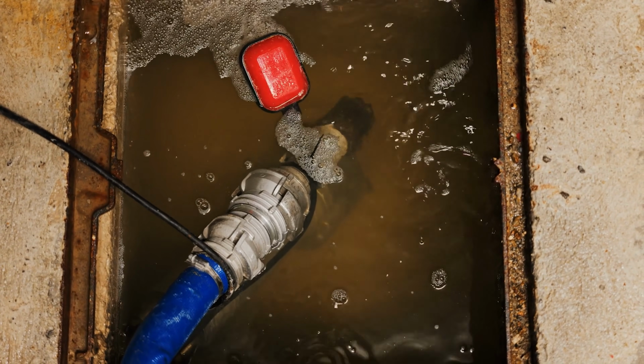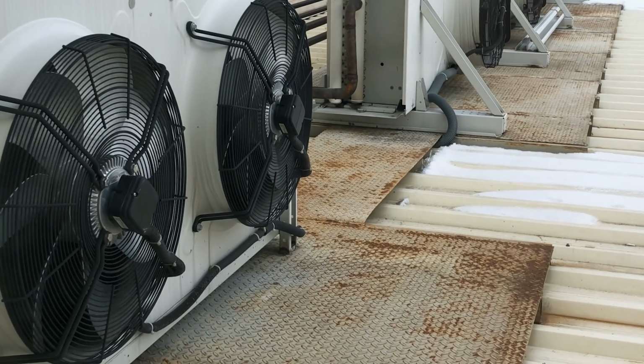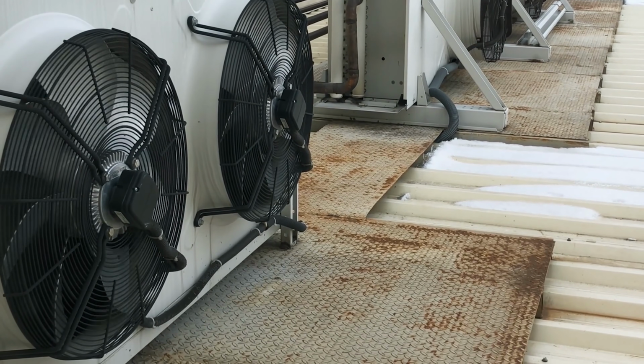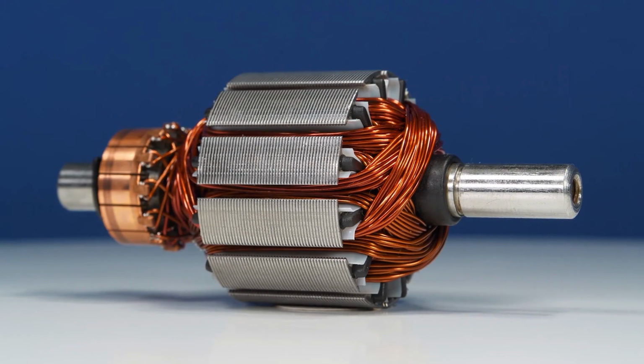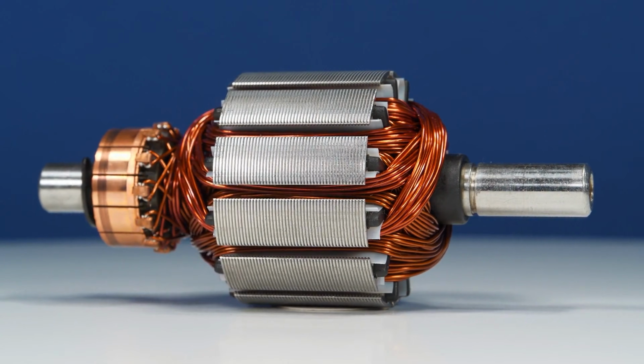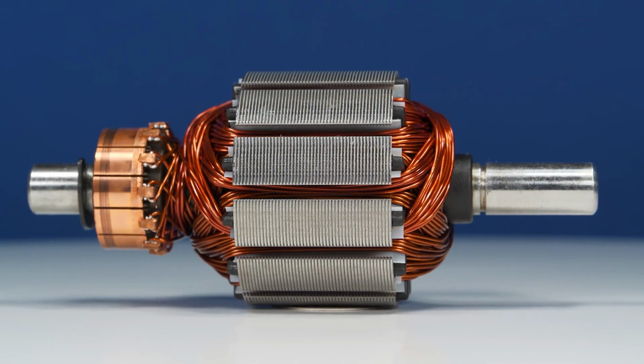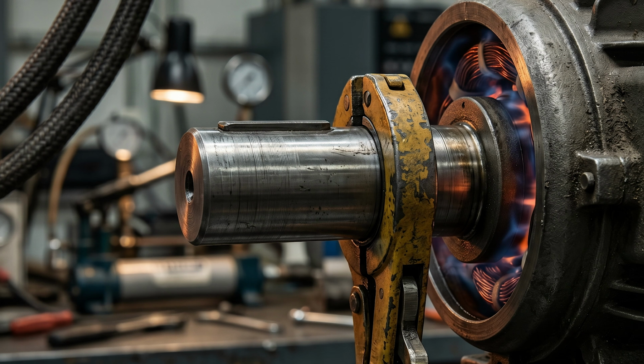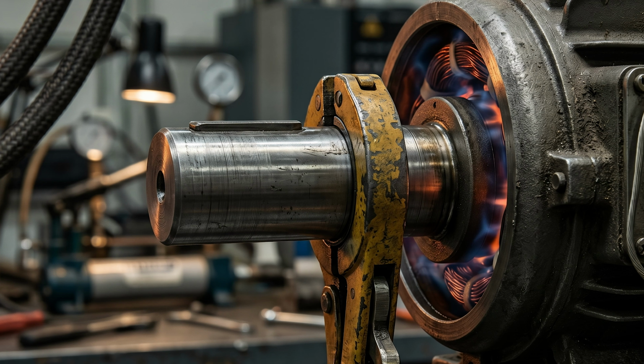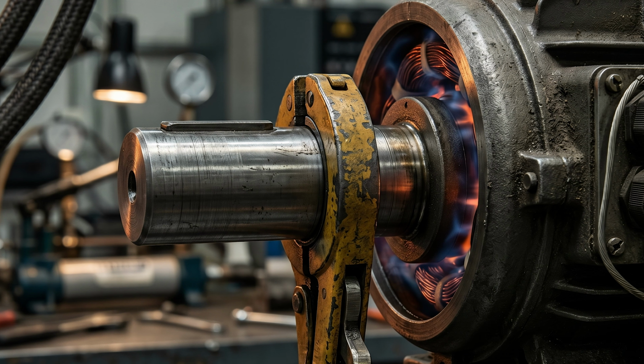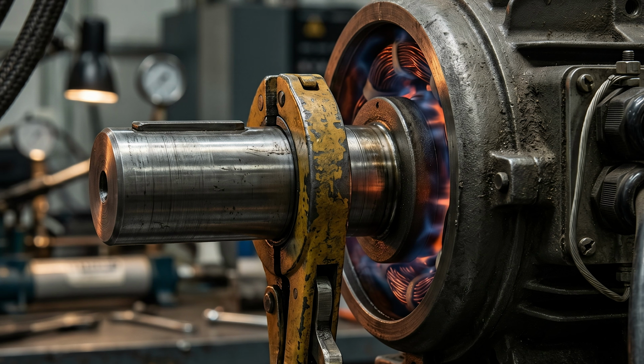Every essential household appliance you own, sump pump, refrigerator compressor, freezer, HVAC blower, runs on an AC induction motor. When that motor is sitting still, it's essentially a short circuit. The moment power hits it, it draws maximum amperage, 3 to 6 times its normal running load, for the first 2 to 3 seconds, until counter EMF kicks in and drops the current back to normal.